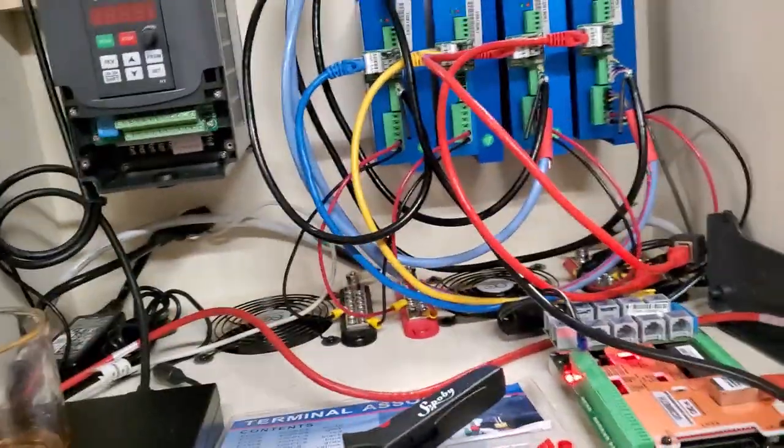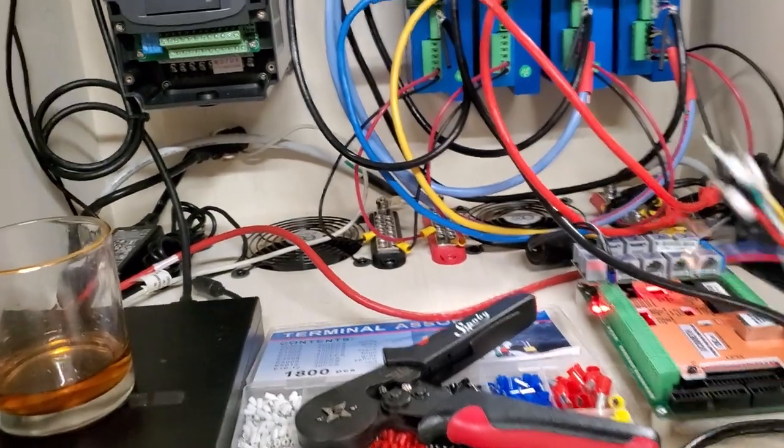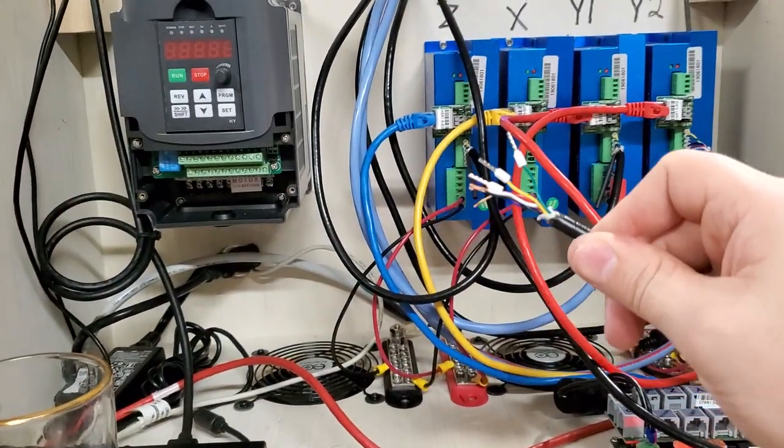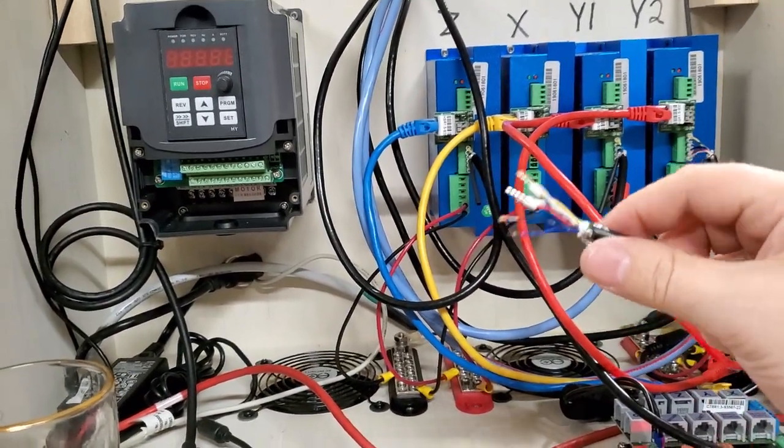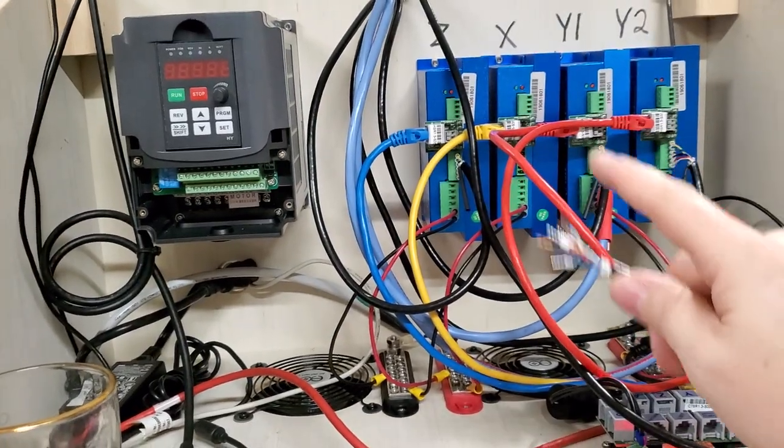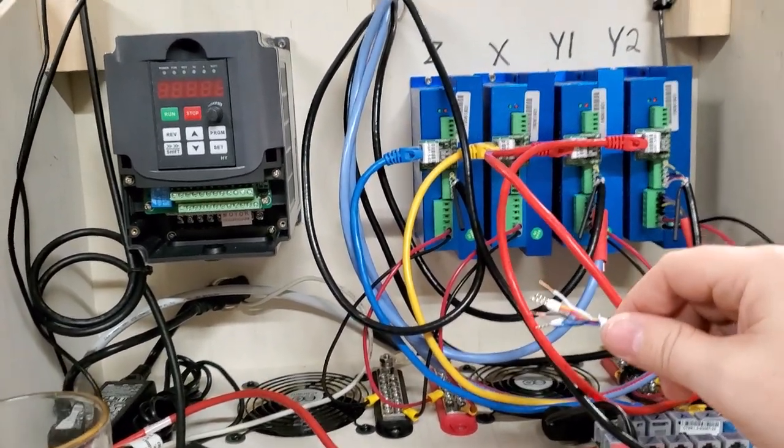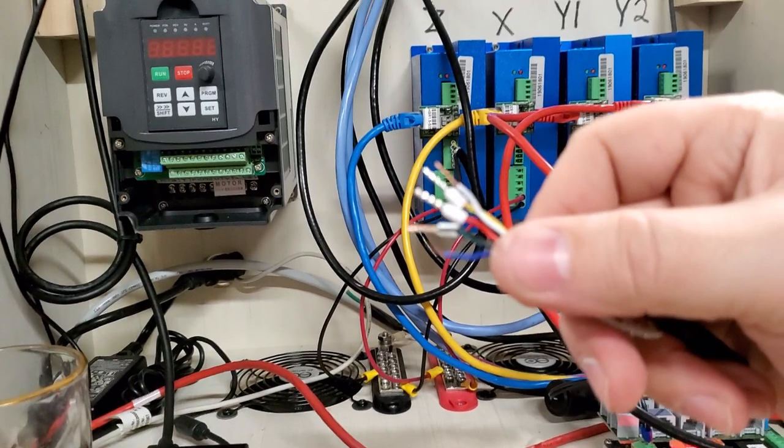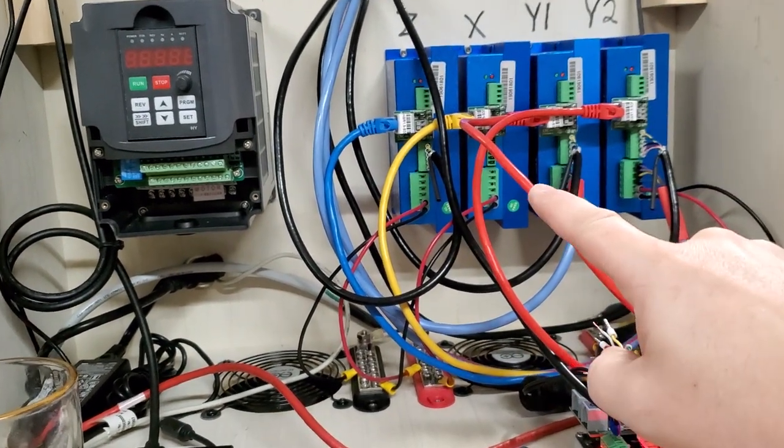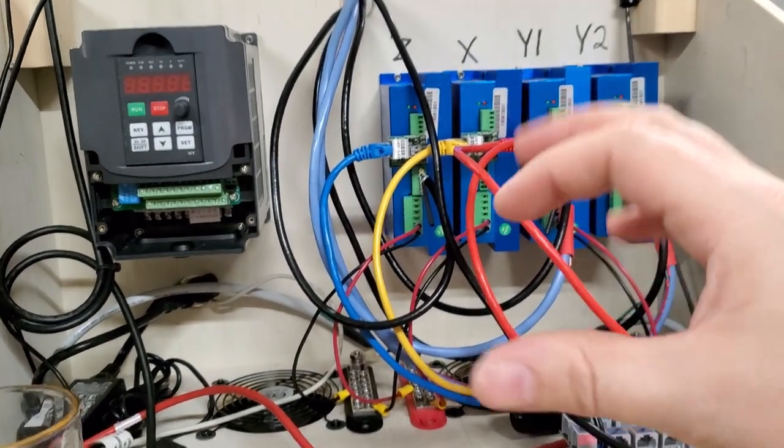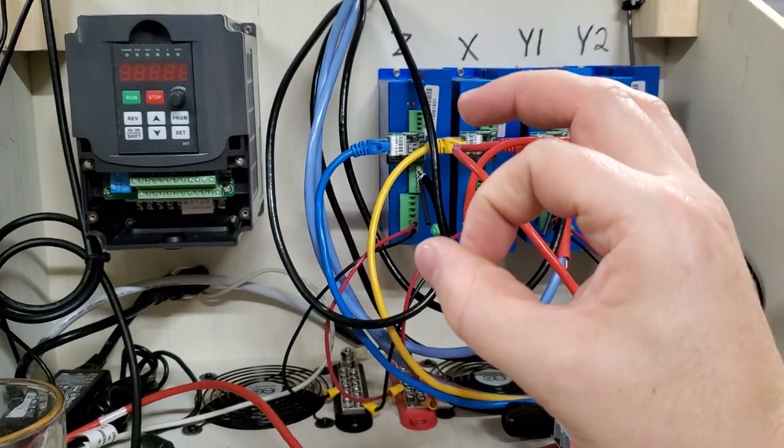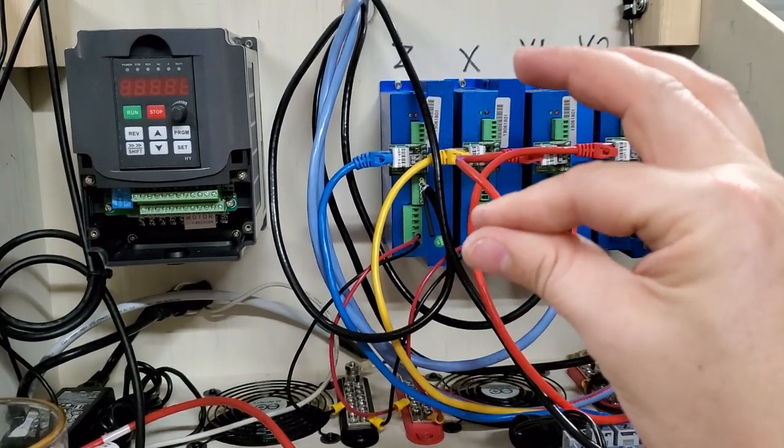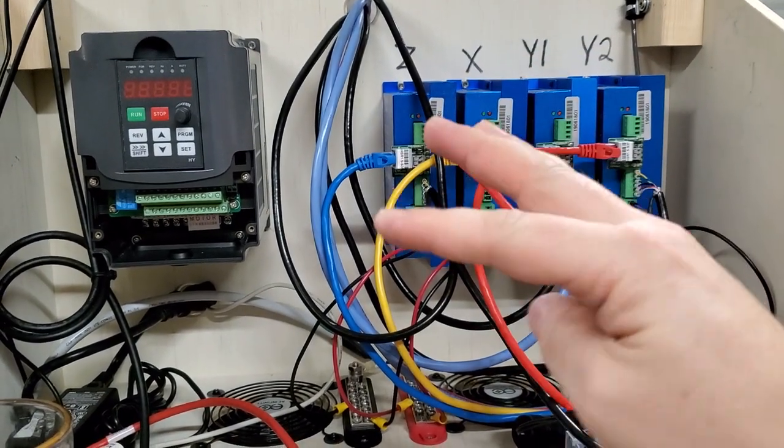Now I have a really good reason for using these on video monitors in operating rooms. I had a brand new Karl Storz video system that was installed and what they did is they stripped back the wires and they screwed them into terminal blocks like that. And when you do that, part of the cable gets pinched down by the screw down, but the other pieces just kind of splinter off and they go around the screw so that you don't get them all.